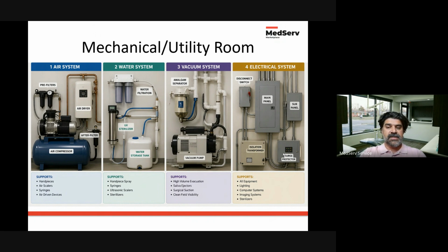Vacuum systems, as you might be familiar, are for the removal of waste. So you have your HVE, high volume evacuators, and your saliva ejectors. These systems operate under negative pressure, so restrictions, leaks, or improper cleaning can lead to a reduction in suction. Typically, there are a lot of traps with little meshes or nets to capture debris that, if they are not looked at or addressed, will typically find their way back upstream into the tubing and plumbing, and that will cause a blockage or some sort of reduction in flow.